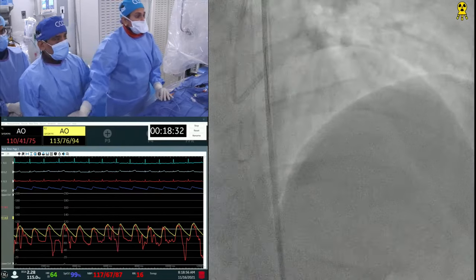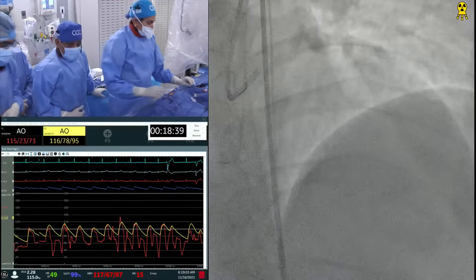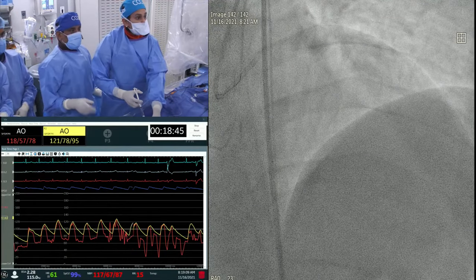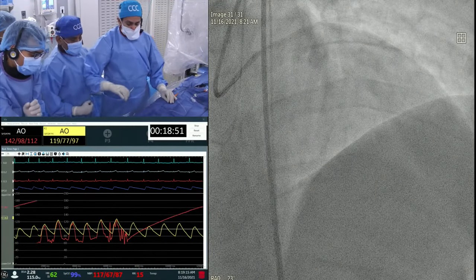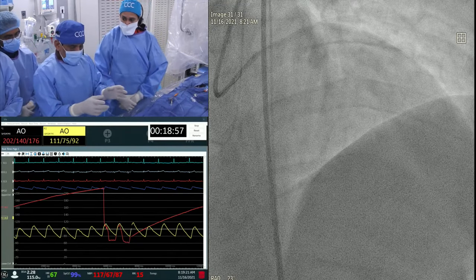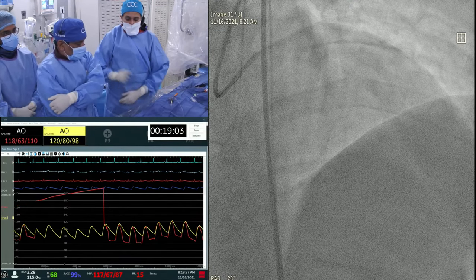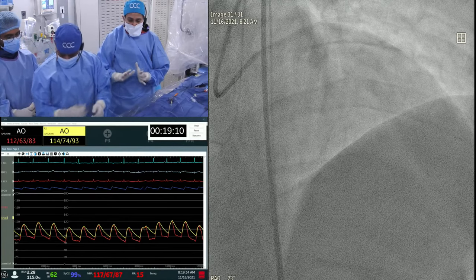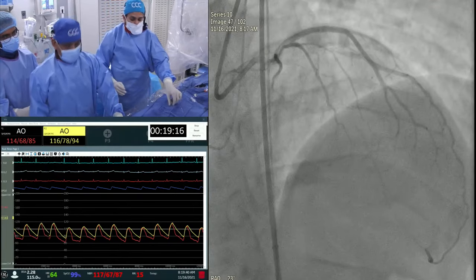A lot of people asked about the Tornus microcatheter. Remember Tornus was the first of its kind, but I would say that after Fine Cross and Corsair, personally I don't see any use of Tornus anymore. The Fine Cross and the latest Corsair Pro XS have a much lower profile and work very well. The Corsair comes in two lengths — 135 and 150, where 150 is for retrograde use. The wires also come in various lengths, all mentioned in the app.